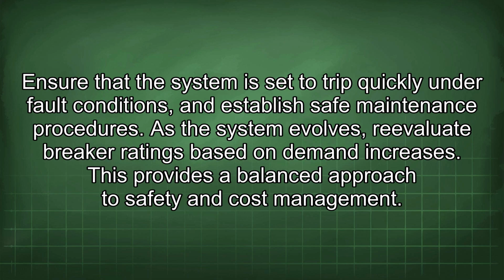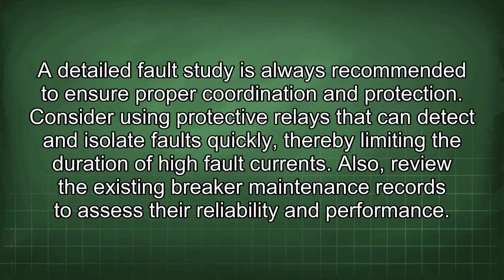Ensure that the system is set to trip quickly under fault conditions and establish safe maintenance procedures. As the system evolves, reevaluate breaker ratings based on demand increases. This provides a balanced approach to safety and cost management. A detailed fault study is always recommended to ensure proper coordination and protection.